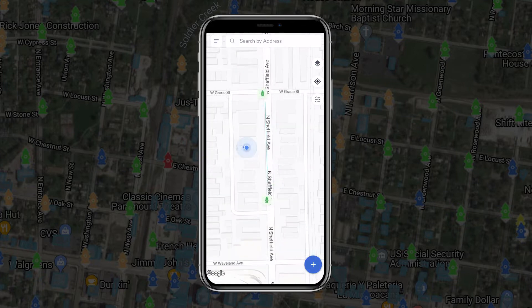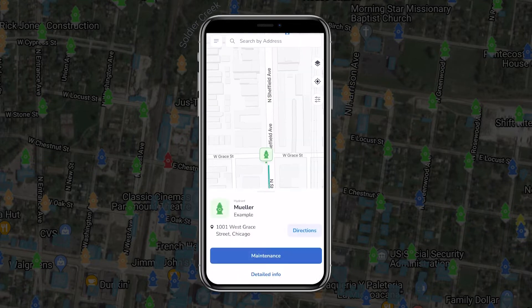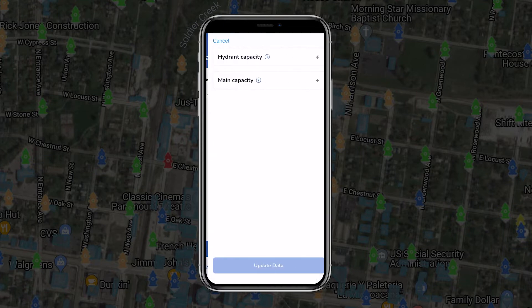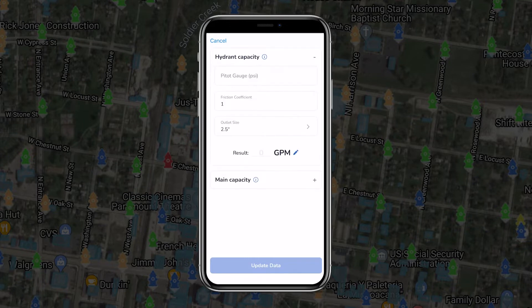The app will allow you to calculate hydrant capacity, as well as main capacity, by selecting your test hydrant, tapping Maintenance, and tapping Calculate Capacity. Hydrant capacity is calculated using Bernoulli's formula, whereas main capacity is calculated using the Hazen-Williams formula.